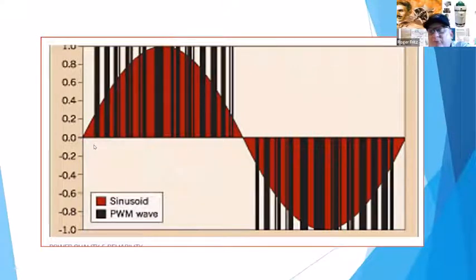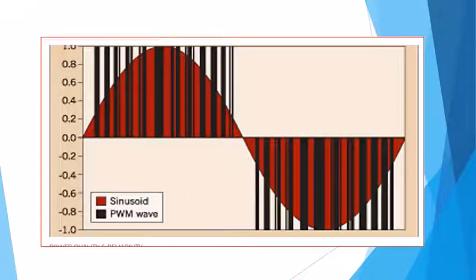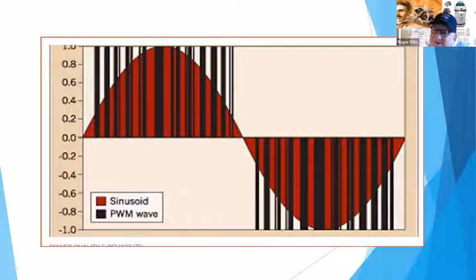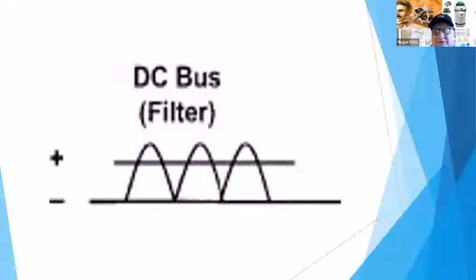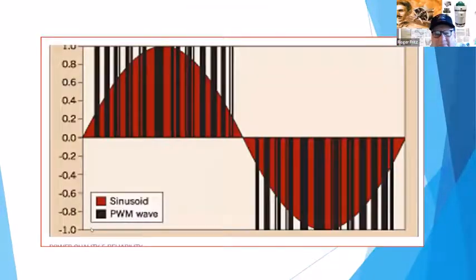That's what we found way back 25 years ago when we were dealing with Milton Bradley toys. We put all these drives on 75 injection molding machines, and all of a sudden the colors of the products were turning different colors. They're going, what the hell's going on? We're kind of scratching our heads because the drive manufacturer didn't really explain all that to us. So we ended up going in and putting some meters on, and then we worked with the power company. We had to put line reactors on the front.